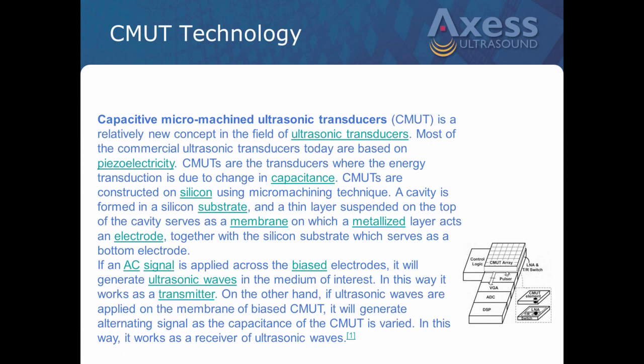Now, as we've talked before, composite arrays and single crystal arrays are all a crystal material, raw earth material that's converted into a crystal and fired to get a piezoelectric effect to generate ultrasound by vibrating that crystal. CMUT is the first technology that's not using a crystal material at all.